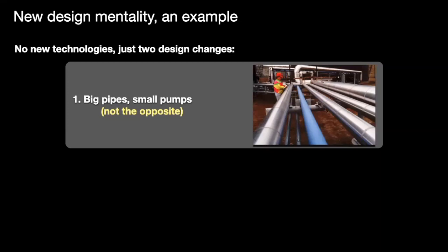Well, the engineering textbooks say to make the pipe just as fat as will repay its extra cost over the years from the saved pumping energy. That seems logical, but it's wrong, because it leaves out the capital cost of the pumping equipment. A pumping system's pump, motor, inverters, electricals all have to be big enough to overcome the friction.